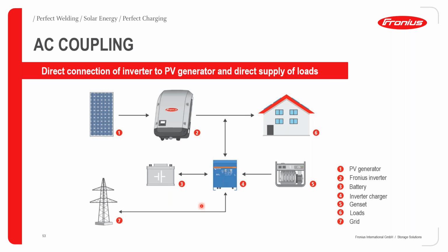But you can also, in this particular example, as you can see, have a situation whereby you are suffering from grid outages from time to time, and therefore this means that your grid is not very stable. And you can have this kind of AC coupled installation as a grid kind of setup with maximum self-consumption. So if you have a situation whereby your peak production from the PV side is matching your peak consumption on the load side, this kind of AC coupled installation makes a lot of sense. And also for systems, let's say larger than 10 kilowatt peak or 10 kilowatt AC, these are systems whereby you can start thinking about AC coupling.